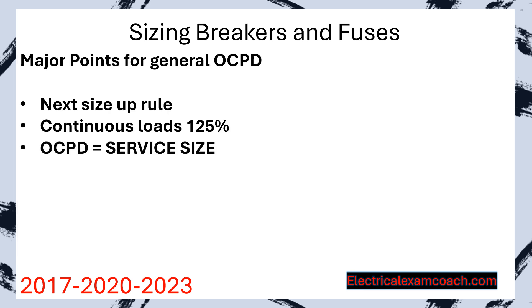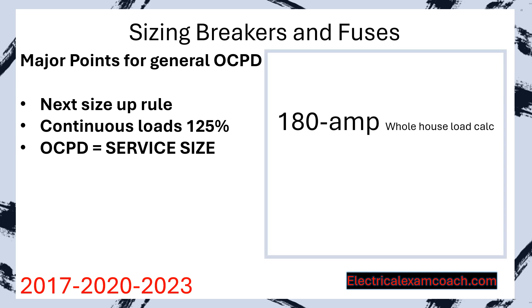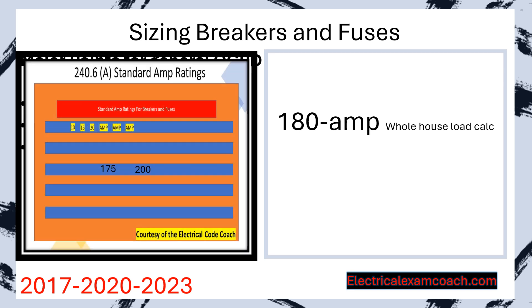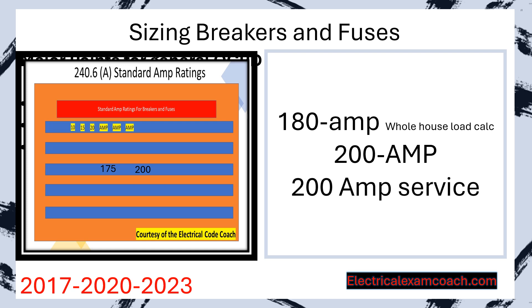Our final major point is that the overcurrent protective device size equals the service size. Let's imagine we did a whole house load calculation and it equaled 180 amps. We have to size the main breaker — we head to Table 240.6A and choose the next standard size, which is 200. The service size is based off the size of the main breaker or main fuse for that structure, so this would in fact be a 200 amp service. The load calculation dictated what size breaker we used, and the breaker size dictated the size of the service — this is very important as we get farther into the program.